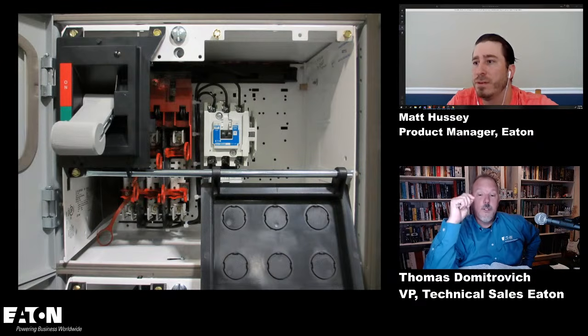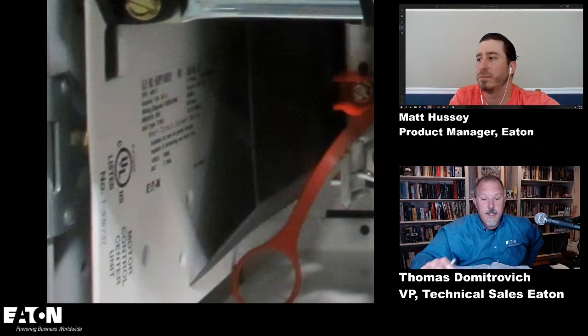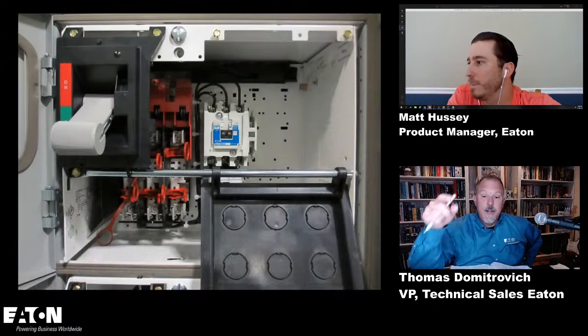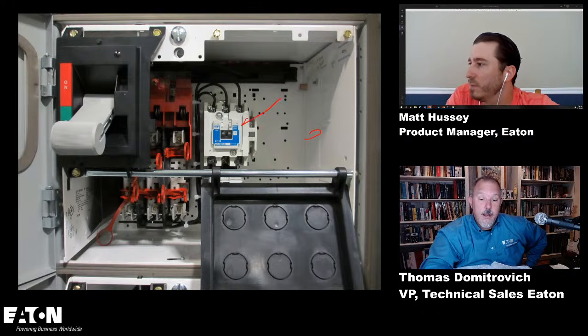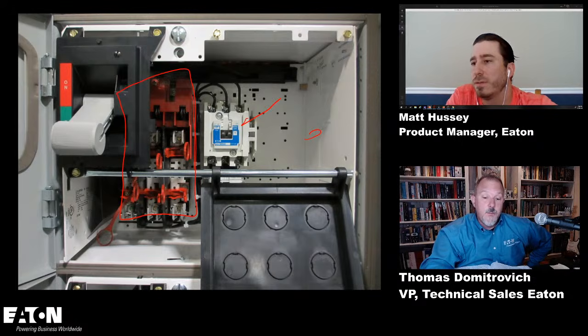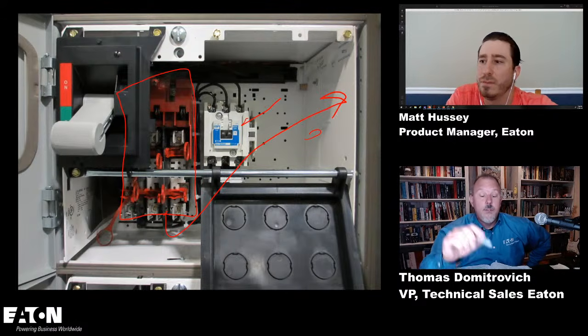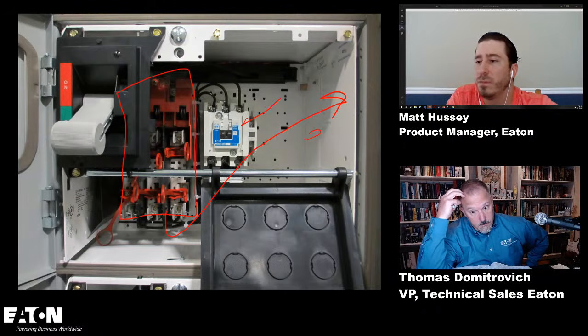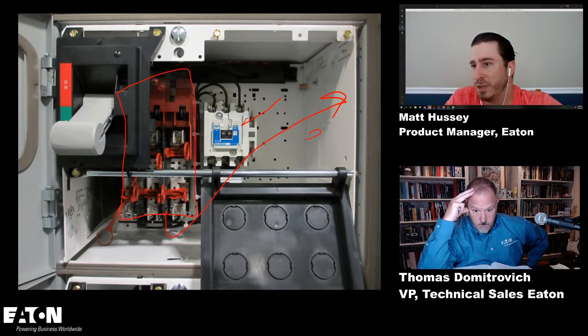Okay, so this is a listed unit, and I did a close up on that label, right? That really shows that unit is listed. Now, Don Ganir asks, can I take this starter out and put in a circuit breaker? Say this was, instead, a fusible disconnect. Can I just go from here and run a feeder out to a panel board and call it a day? Am I allowed to do that? Yeah, you might need a field evaluation to make sure there's nothing wrong with it. Obviously you're changing it from a starter unit to a feeder application. Right. That unit as it was originally listed was a starter compartment. So you might need a follow-up just to make sure that all the components are adequately sized and whatnot.